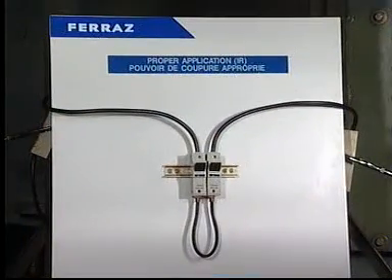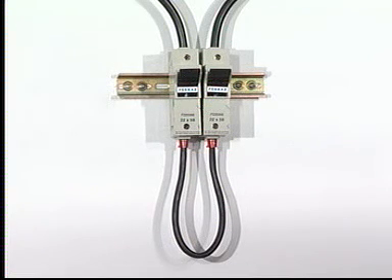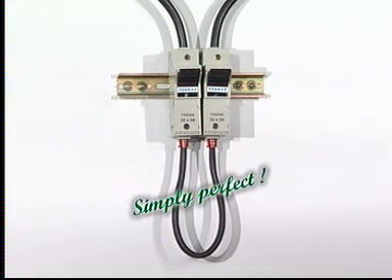The fourth and last test shows fuses with an adequate interrupting rating of 200,000 amperes exposed to the same 25,000 ampere fault. The fuses open safely. Fuses are sealed devices. Resultantly, there is no outgassing to the surrounding area.